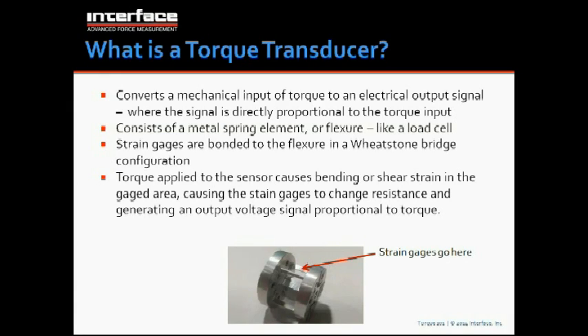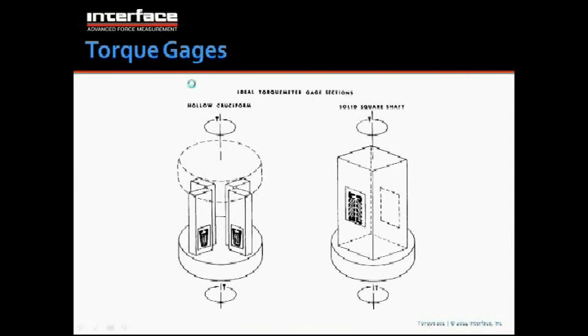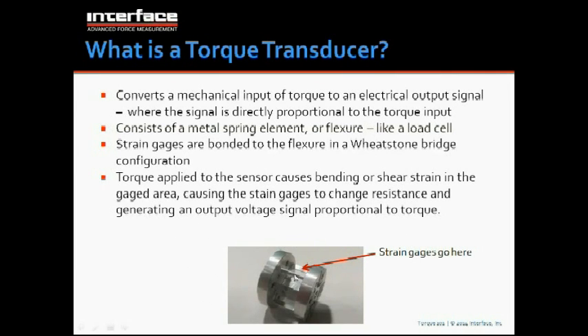This is the basis of torque measurement using foil strain gauges, where a flexure element deflects, and that is converted into an electrical signal that can be correlated to applied torque. You can see in my picture, this is one of our model MRT torque sensors. And you can see the strain gauges would go on the sides of these beams, and that would be in a bending configuration.